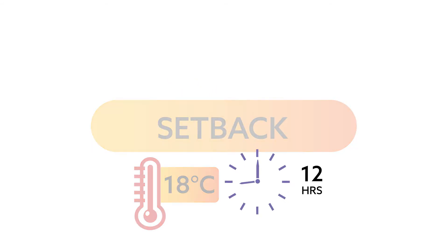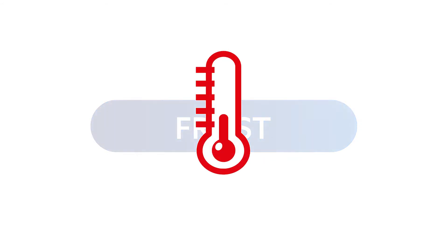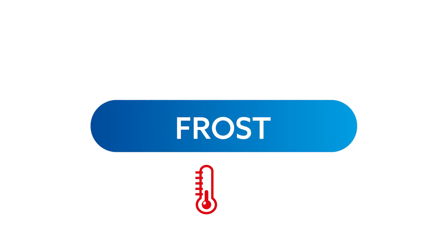If the room is empty for a longer period — typically 12 hours — the Ecostat 2 enters frost mode. The heater is turned off, the temperature drops, and then Ecostat 2 protects the room by keeping it at the preset temperature, usually around 5 degrees C.